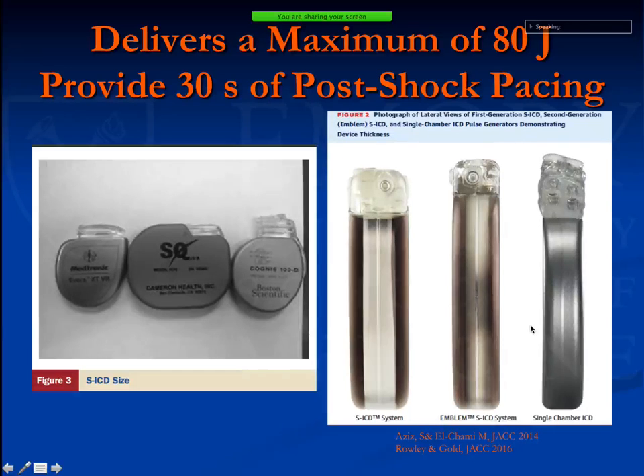If you look at this defibrillator, it delivers a maximum of 80 joules and provides only 30 seconds of post-shock pacing. It doesn't do any backup pacing. And because it has to deliver 80 joules as opposed to 35 or 40 joules from a transvenous device, it had to be bigger. So the size is almost twice. If you look at the newer generation, even though it's thinner, it's a little bit taller. This is the newer generation, and this is the older generation.